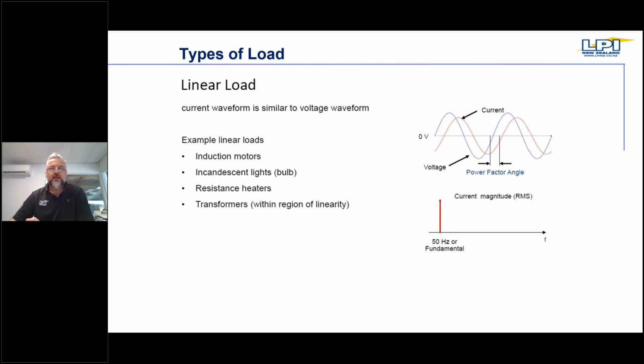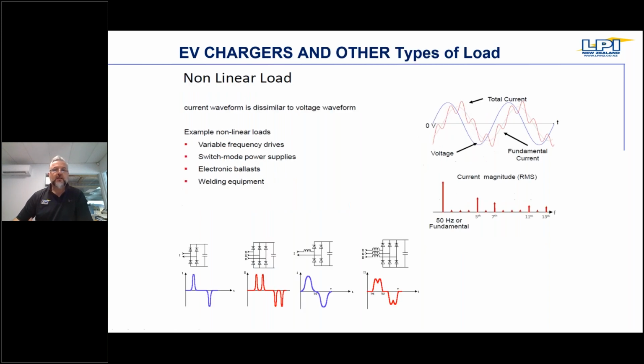Types of loads, for example: you can see here that in this situation there are no harmonics in this system because these are linear loads. With linear loads you don't have any problems as long as you've got resistive loads, induction motors and transformers; they would not cause harmonics. While if you use EV chargers or VSDs, variable frequency drives, and switch mode power supplies, they would cause harmonics, and they can cause these problems that I mentioned earlier.